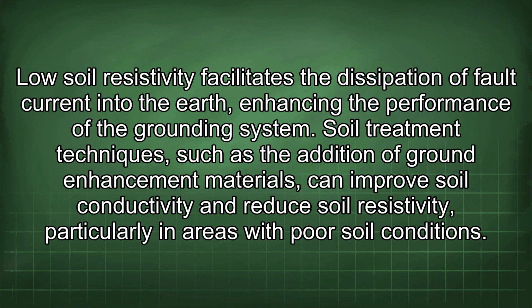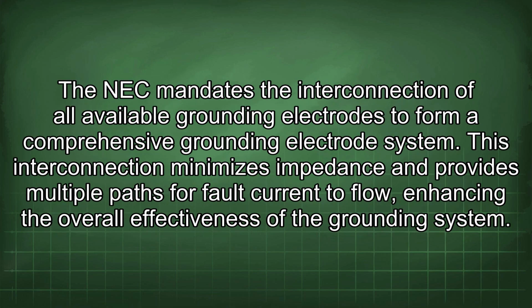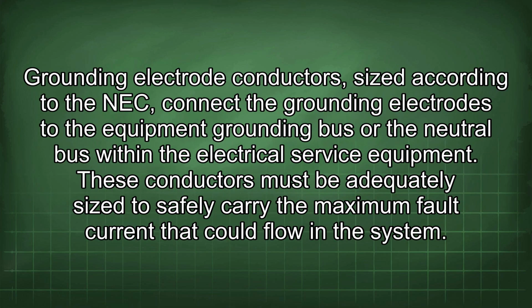Low soil resistivity facilitates the dissipation of fault current into the earth, enhancing the performance of the grounding system. Soil treatment techniques, such as the addition of ground enhancement materials, can improve soil conductivity and reduce soil resistivity, particularly in areas with poor soil conditions. The NEC mandates the interconnection of all available grounding electrodes to form a comprehensive grounding electrode system. This interconnection minimizes impedance and provides multiple paths for fault current to flow, enhancing the overall effectiveness of the grounding system. Grounding electrode conductors, sized according to the NEC, connect the grounding electrodes to the equipment grounding bus or the neutral bus within the electrical service equipment. These conductors must be adequately sized to safely carry a maximum fault current that could flow in the system.